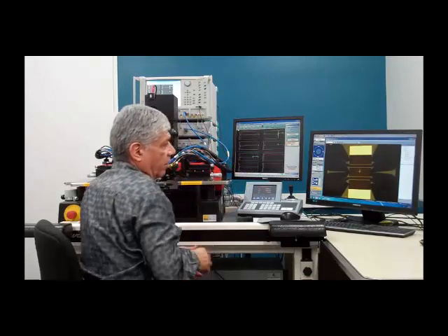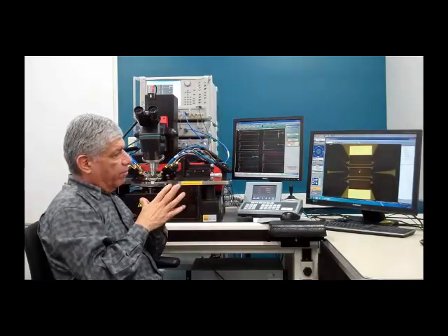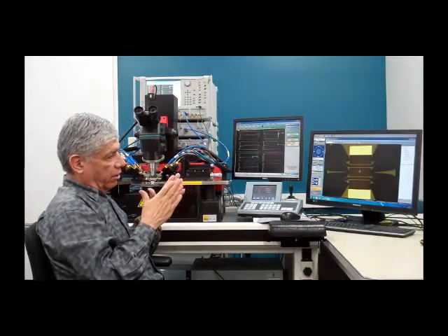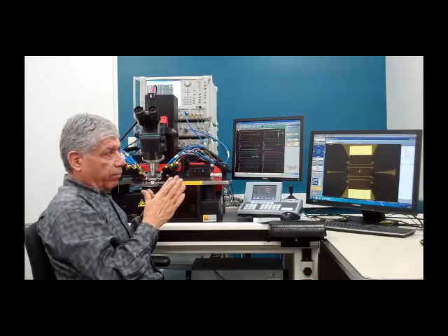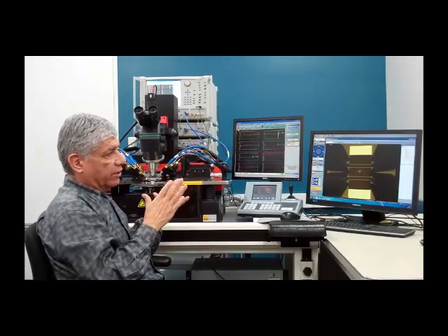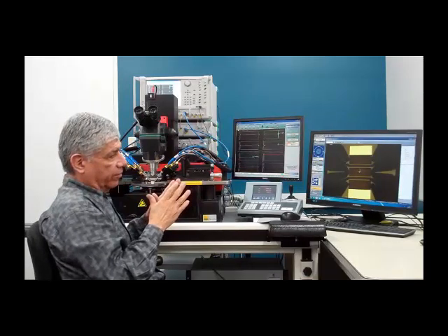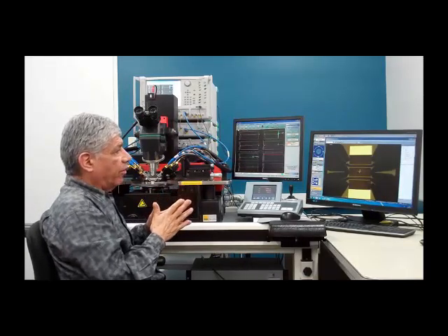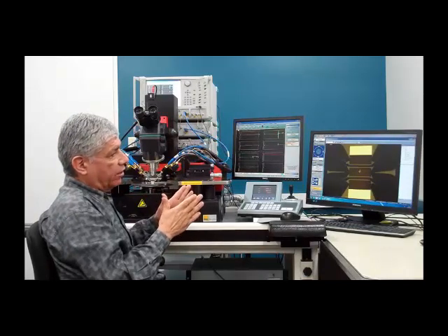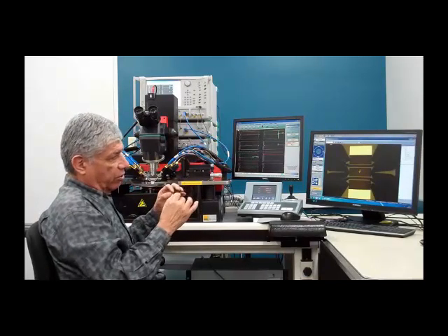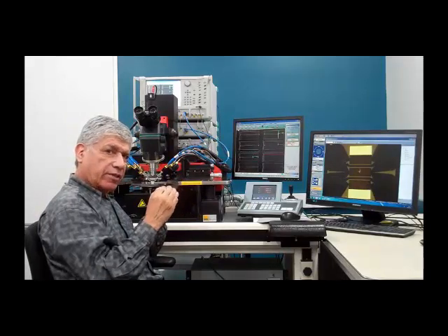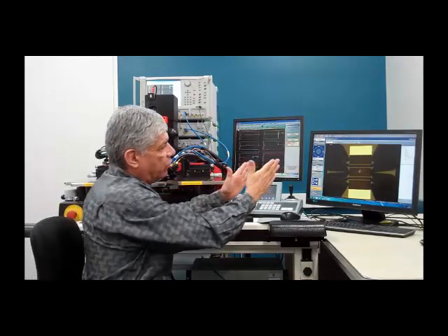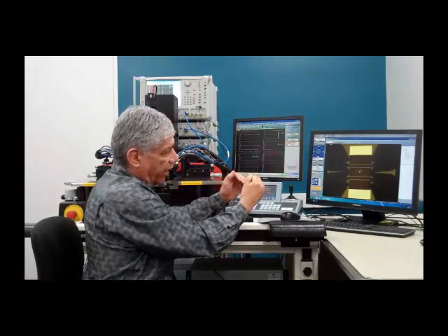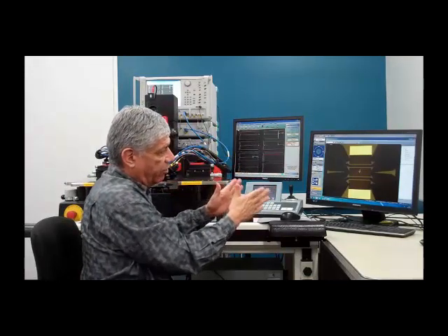And here it's important to make sure that the separation is close to where the standard is defined. So in other words, with the proper skating, when you land on the throughs, you should be exactly 4 picoseconds apart. If you come in too far, for instance, and then land and skate inwards and you end up with less than 4 picoseconds of separation, that's going to throw off your calibration.